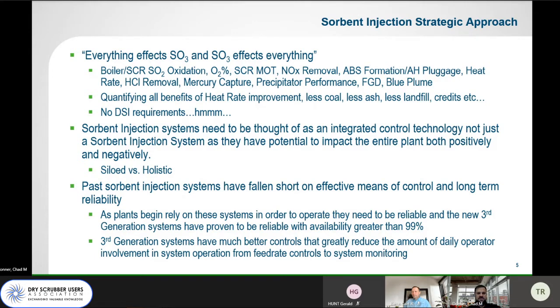And again, sorbent injection systems, I think, need to be thought of as an integrated control technology, and not just a standalone environmental control system, because they can affect the entire plant both positively or negatively depending on the controls in place. So taking the siloed versus holistic challenge at heart, and trying to apply a holistic look at it. And I would say in the past, dry sorbent injection systems have fallen short on means of control and long-term reliability. And again, as plants begin to rely on these systems to achieve these benefits to compete in the changing market, the reliability needs to be there to back those systems up. And again, third generation systems, I believe we have the ability to do that.